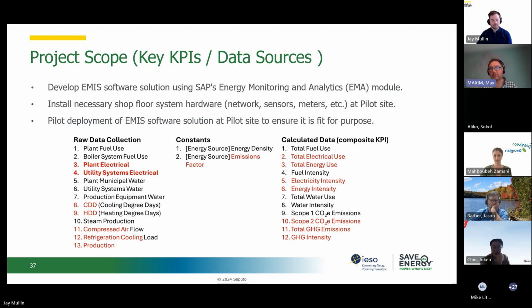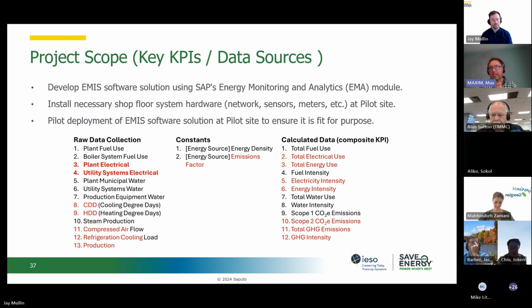With electrical metering and sub-metering, one of the hardest things was educating the folks doing the dashboard programming and the aggregation from the sub-meter, because a sub-meter can often measure data every second, but if you're transmitting data every second, you'll quickly fill your data storage and it'll cost a fortune. So we might aggregate every 5 seconds, every minute, or every 15 minutes. Trying to explain the difference between aggregating for kilowatt hours versus kilowatts was painfully frustrating, but I think we got there, and I've got a method to do that simply going forward. Just something to be aware of.